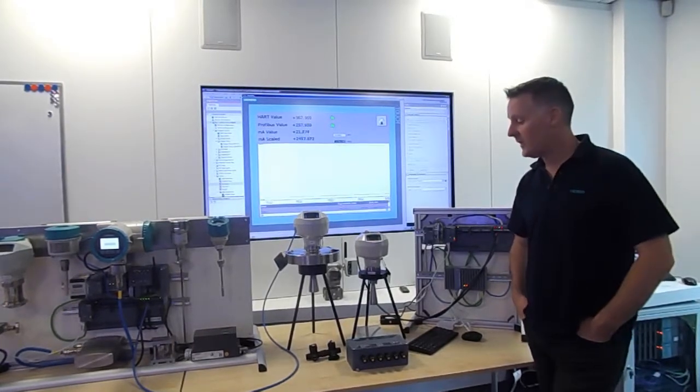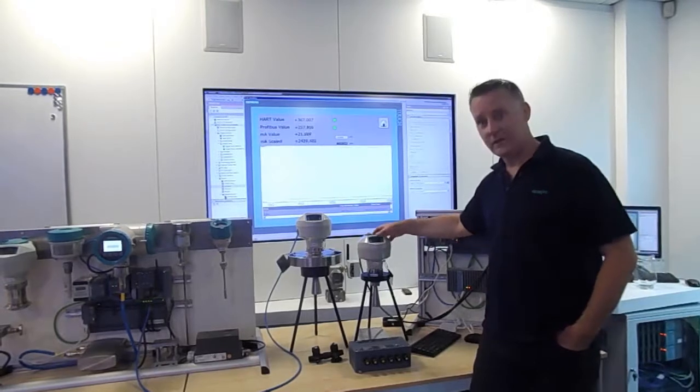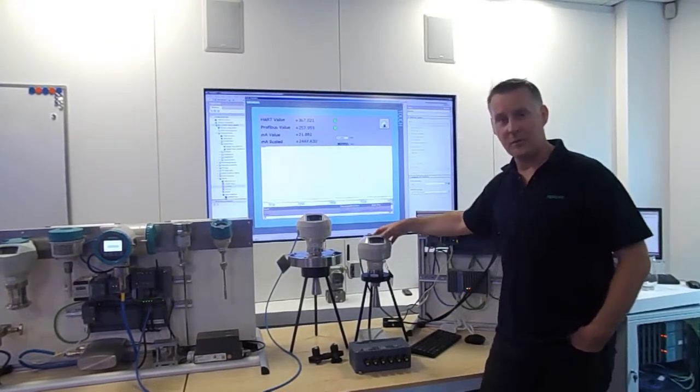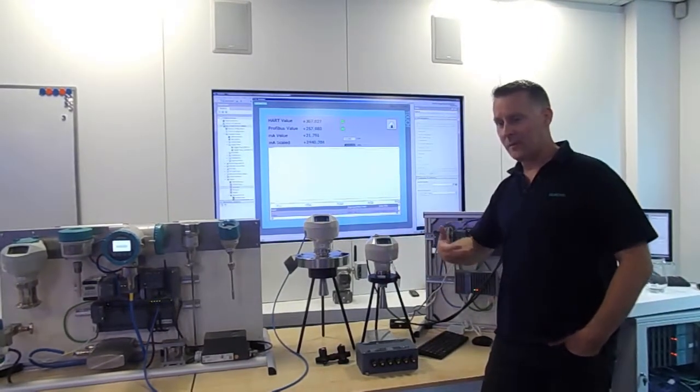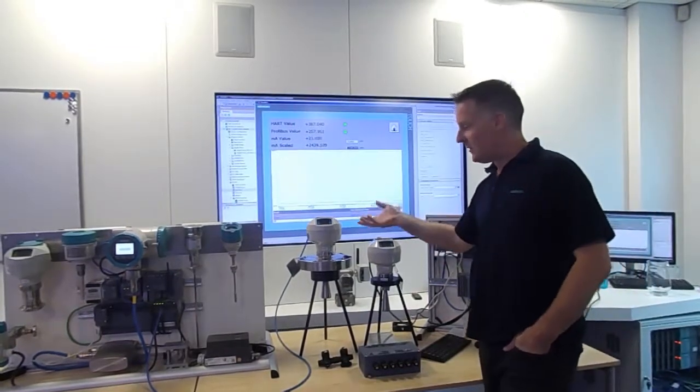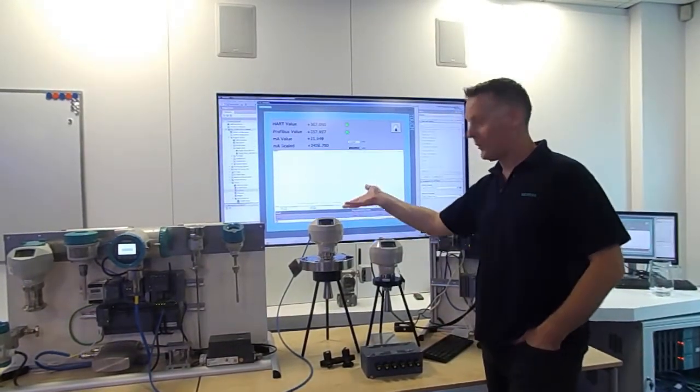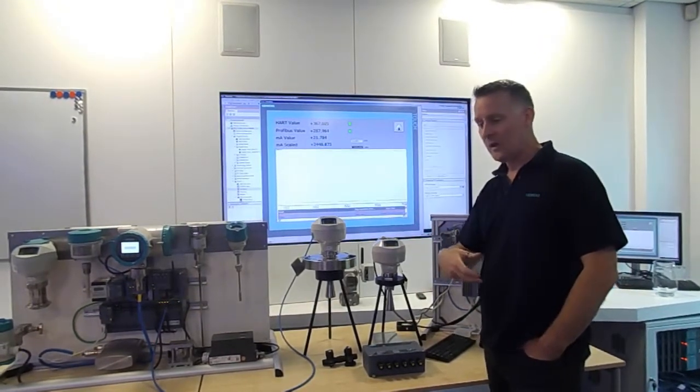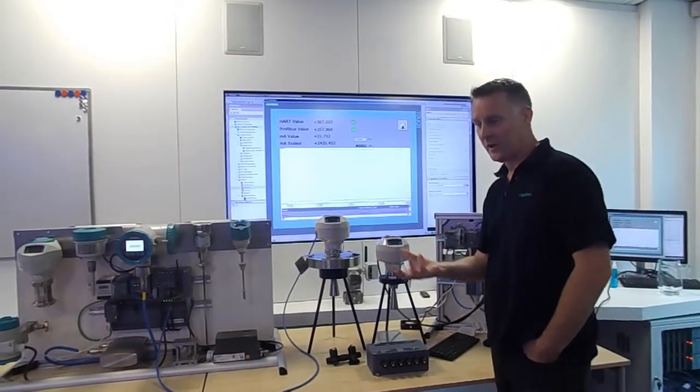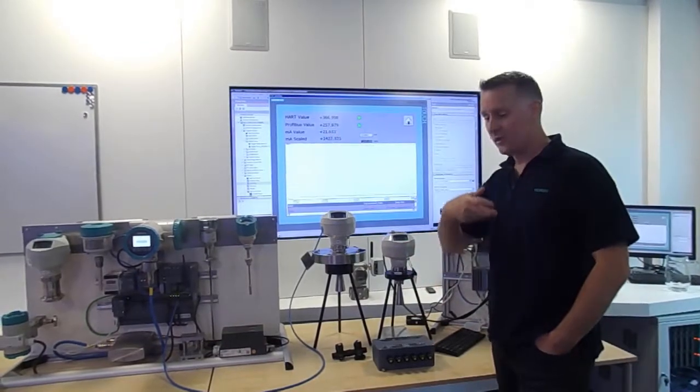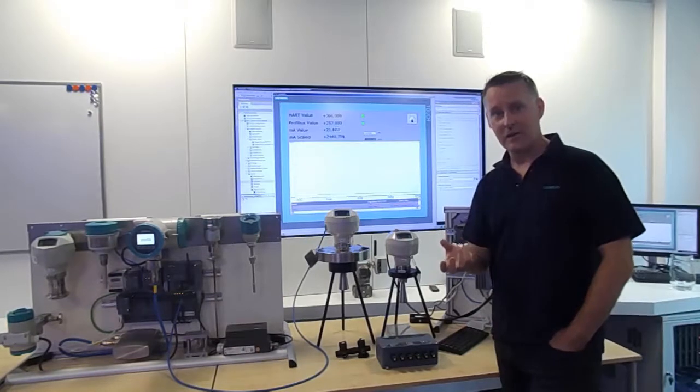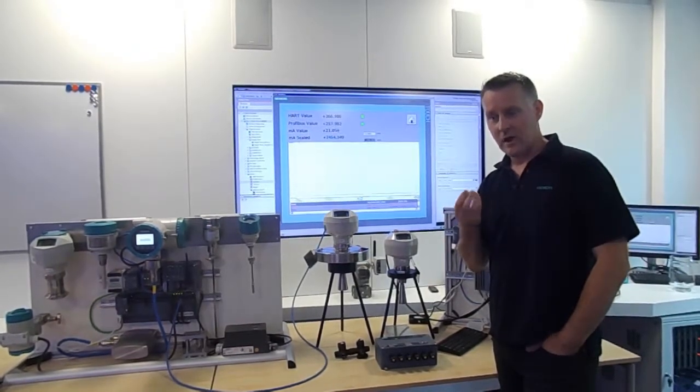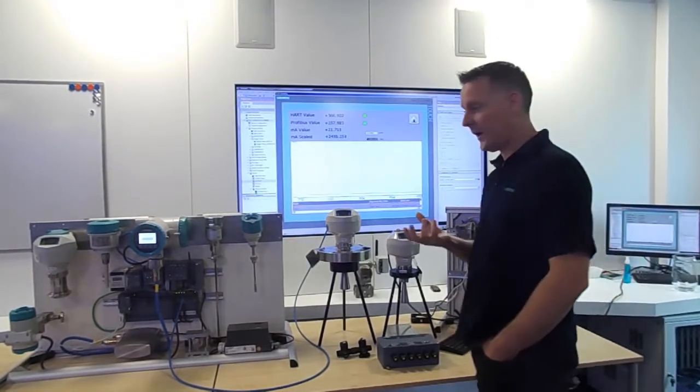So to summarize the findings, what we need to take into account is we've done some accelerated aging here. We've been pretty brutal with the water that we've put into the junction box. Normally water ingress happens over a prolonged period. So you wouldn't get any sudden indication until you got to this point of saturation. With a small bit of water in on a milliamp signal it would be more prone to picking up noise because you're now shorting the signal to earth. So you're creating noise loops. So you might start to see signals jumping around. But you would definitely see, with a small amount of water ingress, some uncertainty on your milliamp value. But your digital value would stay okay.